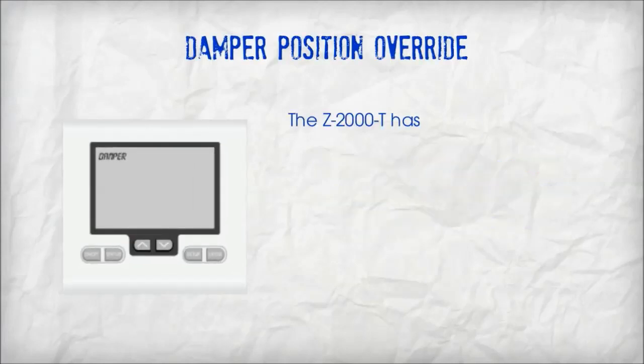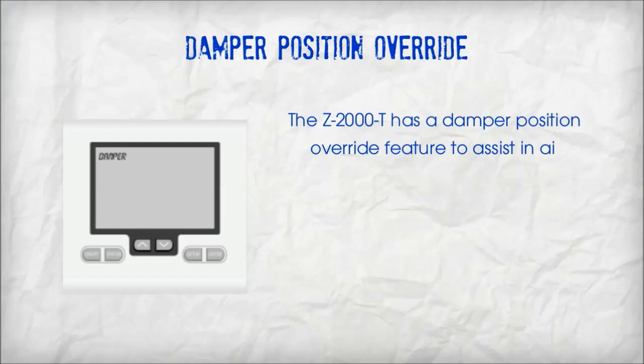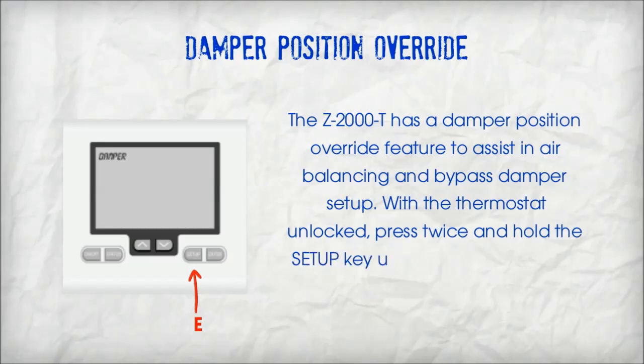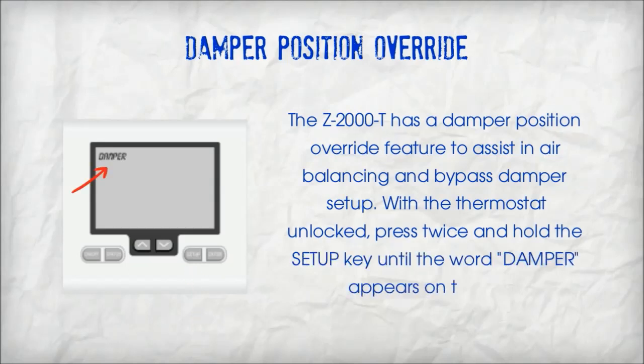The damper position override. The Z2000T has a damper position override feature to assist in air balancing and bypass damper setup. With the thermostat unlocked, press twice and hold the setup key until the word 'damper' appears on the LCD.